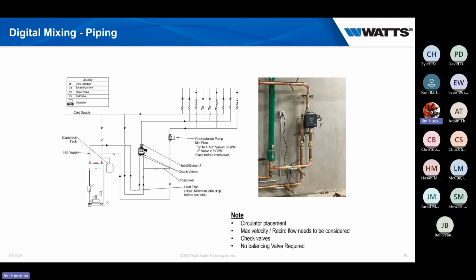So a couple of the other features we run into — and a lot of my problems, I know nobody on this webinar sizes anything incorrectly, but for people that aren't on this webinar, I do get a lot of piping issues, so I put this one up there. A couple of features when we're piping in or designing one of our systems: we always want our circ pump, and please make sure this circ pump is upstream of our cold water bypass. We want this water pushing through our cold water bypass and then heading back to that boiler. This is just a feature setup showing what it looks like actually in the system, with all the additional sensors wired up. It's a really nice, clean look.